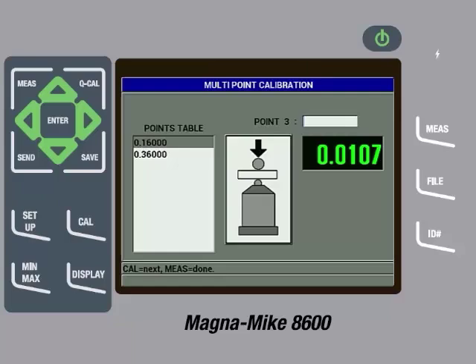The instrument will start displaying a measurement. Once the reading on screen is steady, we will press the Cal key. Once the instrument is finished processing, we will use the arrow keys to change the value to the exact thickness of the shim, which in this case is 0.0100 inches or 0.254 millimeters. We will then press the Cal key, which will add this thickness to the list of calibration points.